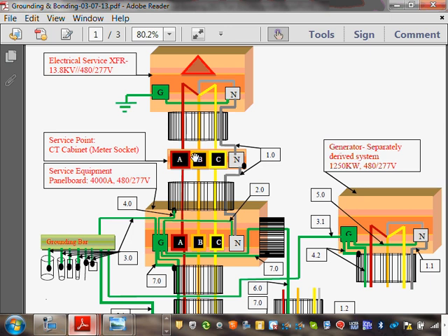This could be your meter socket, could be your CT cabinet. If it's a small system, your meter socket, right? If it's a bigger system, we call them CT cabinet, 400 amp or higher, we start putting a CT cabinet. So you put your conduits here, the utilities pull your conductors, depending what you do. This is owned and operated by the utility up to the CT cabinet. You pulled your conductors, 3 conductors, color-coded per industry, for 480/277, and the green neutral coming in. So you're pulling a neutral in.